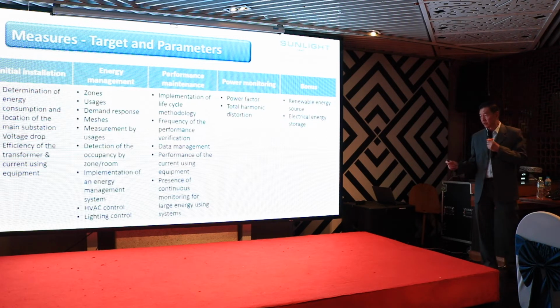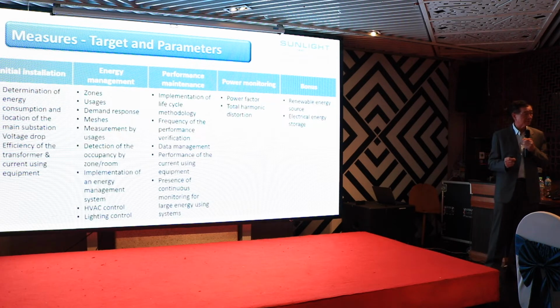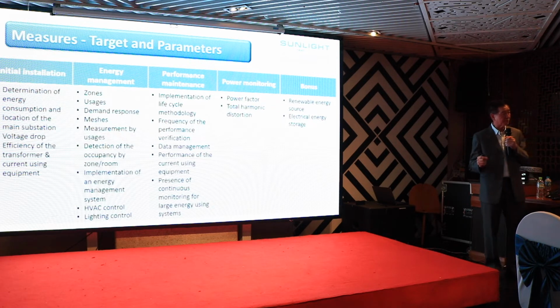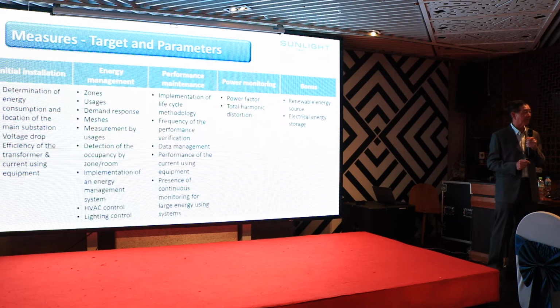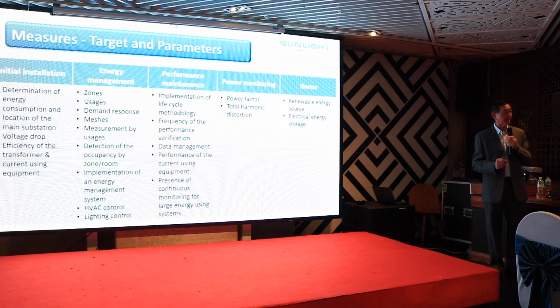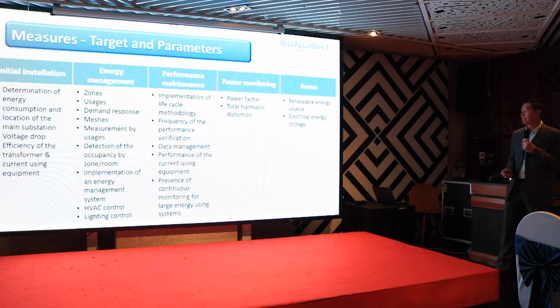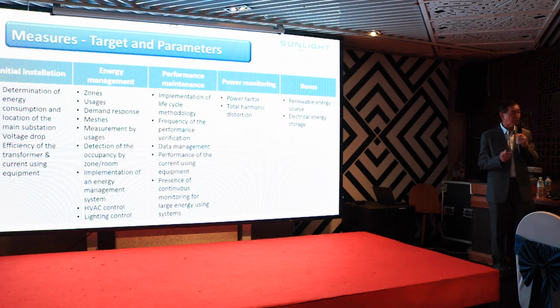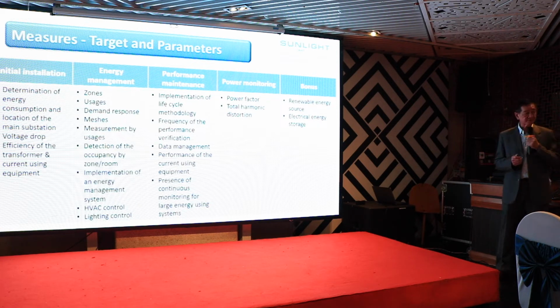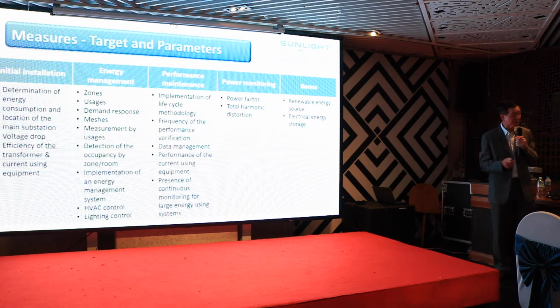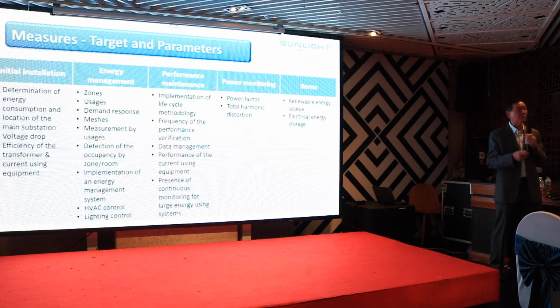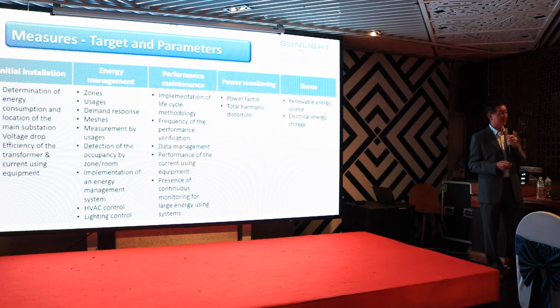Presence of continuous monitoring - it's best that, whatever you can, you do on a continuous basis, measuring temperature at certain spots and the like. Also monitor the quality of power, because harmonics are one of the key presences in data centers, and harmonics can create unnecessary losses. So you must also measure that.